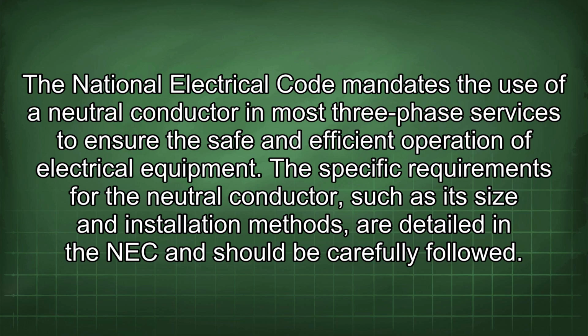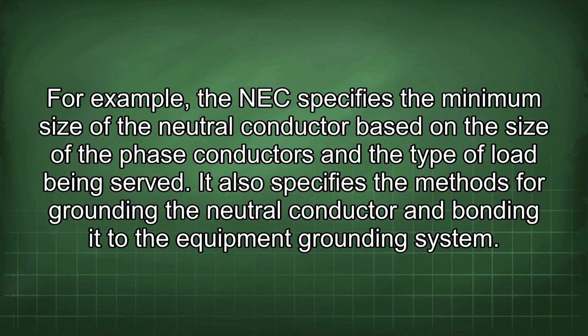The specific requirements for the neutral conductor, such as its size and installation methods, are detailed in the NEC and should be carefully followed. For example, the NEC specifies the minimum size of the neutral conductor based on the size of the phase conductors and the type of load being served. It also specifies the methods for grounding the neutral conductor and bonding it to the equipment grounding system.